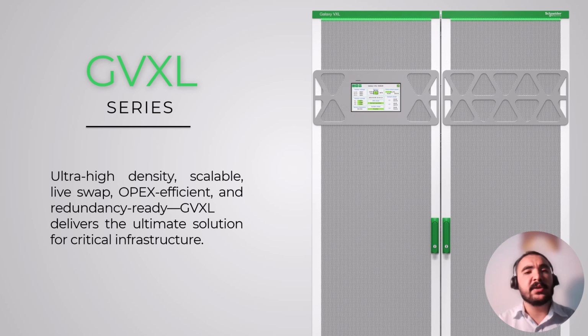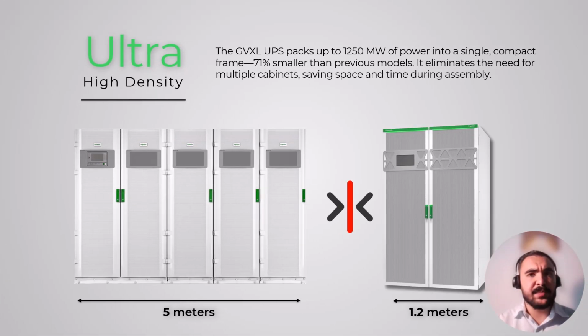Let me start first by defining what I mean by ultra-high density UPS. Ultra-high density means more power packed into a smaller, compact design UPS. Now, the Galaxy VXL UPS can handle up to 1,250 kilowatt of power under one frame, which is incredible. If you take a deep look at the comparison between the previous UPS system that you used to offer for similar kinds of applications, the Galaxy VX, and the current new model, the Galaxy VXL UPS, both units deliver the same amount of power, or the Galaxy VX delivers a slightly higher power, but the key difference lies in space efficiency. Let's assume that the partner or client would like to proceed with the Galaxy VX, and he would like to request 1.25 megawatt of power.